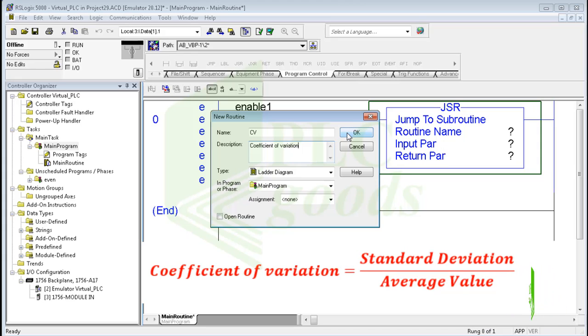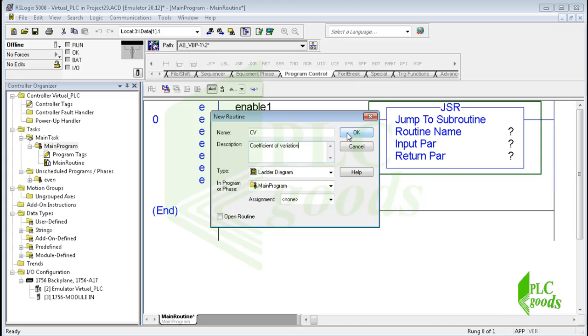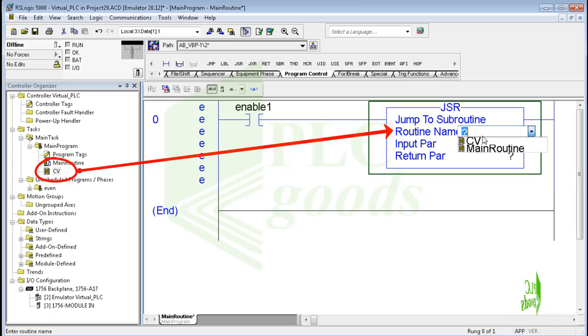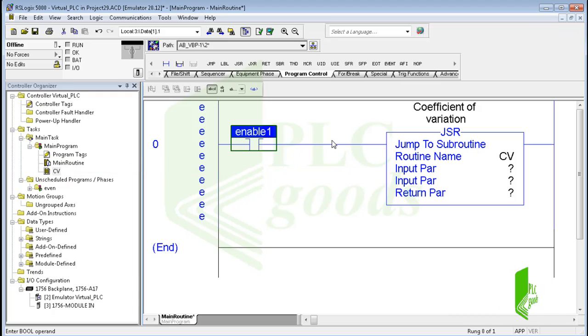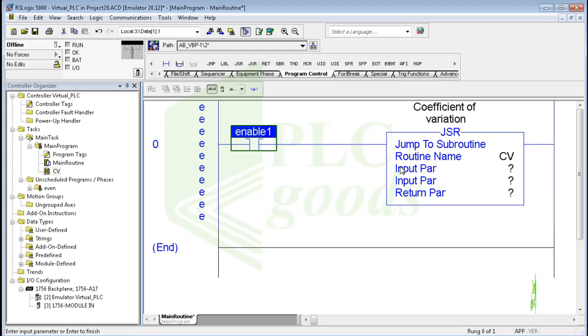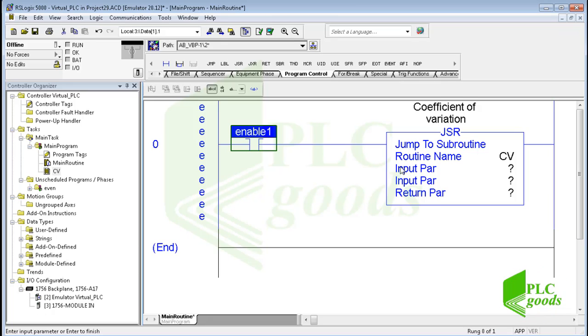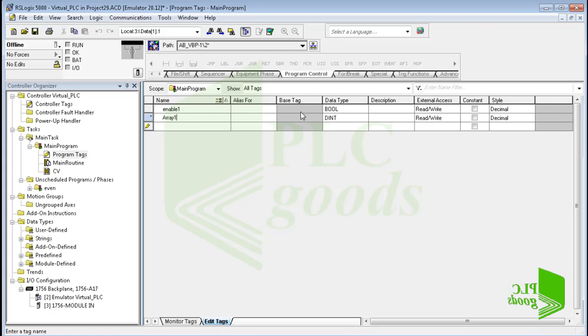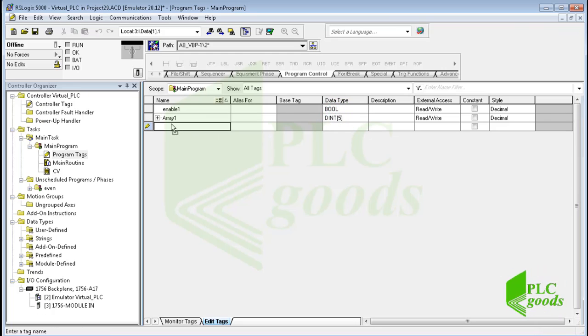Naturally, I select the second choice to calculate the CV parameter, so the CV program won't be repeated in my program but can be used many times. I create this subroutine and call it using the inserted JSR instruction. Until now we used the JSR instruction without any input or return parameters, but now the CV subroutine must receive numerical data and return their CV value. Let me open the program tags table to define some tags — two arrays with five elements and two tags with real data type to store the coefficient of variations.